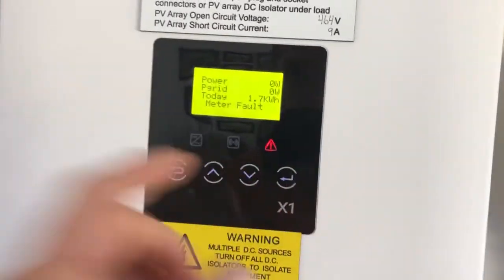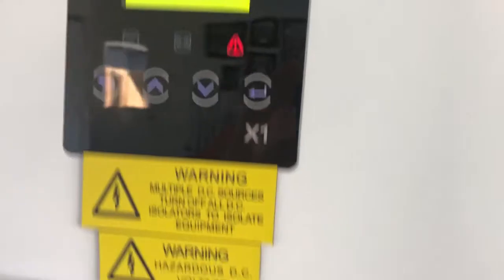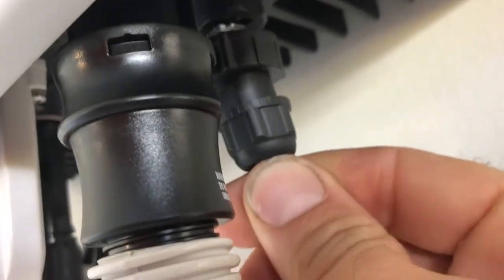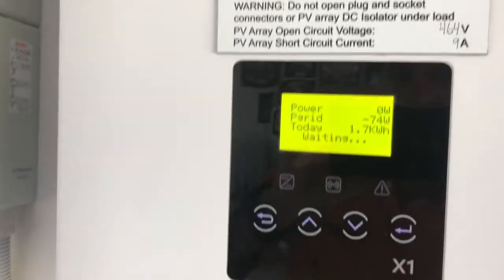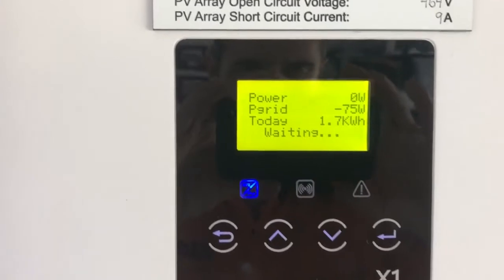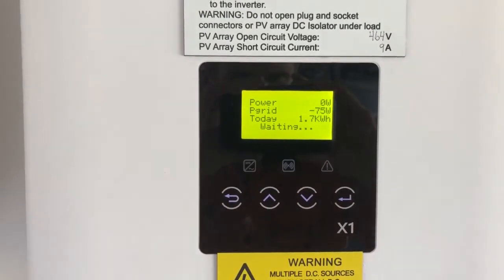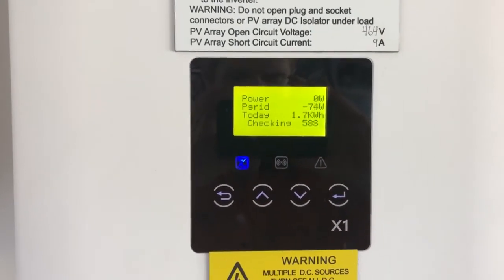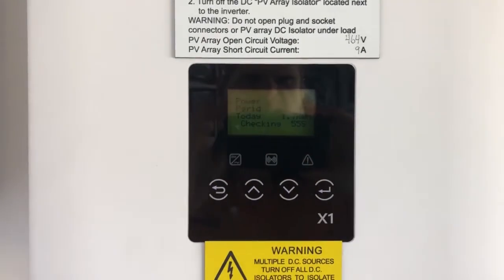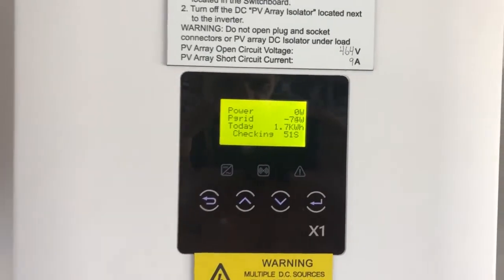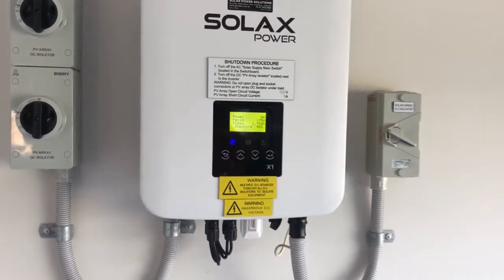We're still showing the meter fault, so I'm going to plug this back in. On the screen now it's got P grid minus 74, meaning we're taking about 74-75 watts from the grid. It's now in a startup procedure and after it's gone through the countdown it should be operational again.